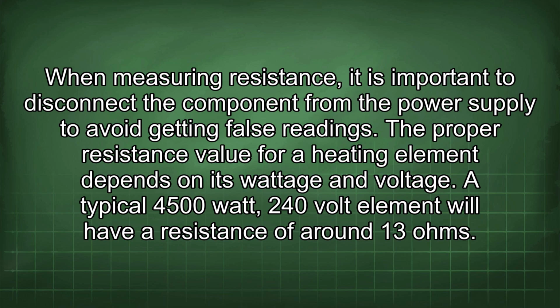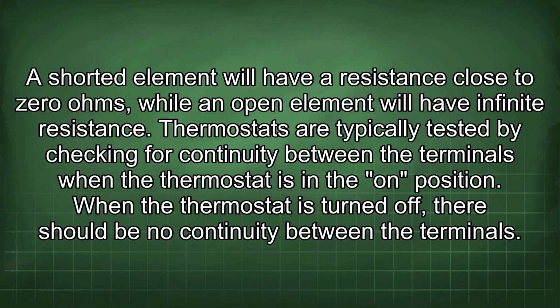The proper resistance value for a heating element depends on its wattage and voltage. A typical 4500 watt 240 volt element will have a resistance of around 13 ohms. A shorted element will have a resistance close to 0 ohms, while an open element will have infinite resistance. Thermostats are typically tested by checking for continuity between the terminals when the thermostat is in the on position. When the thermostat is turned off, there should be no continuity between the terminals.